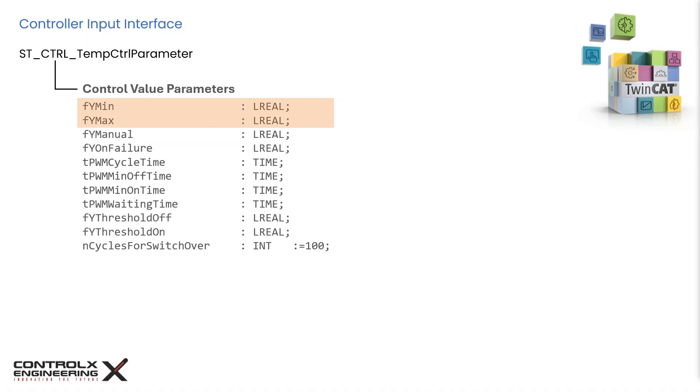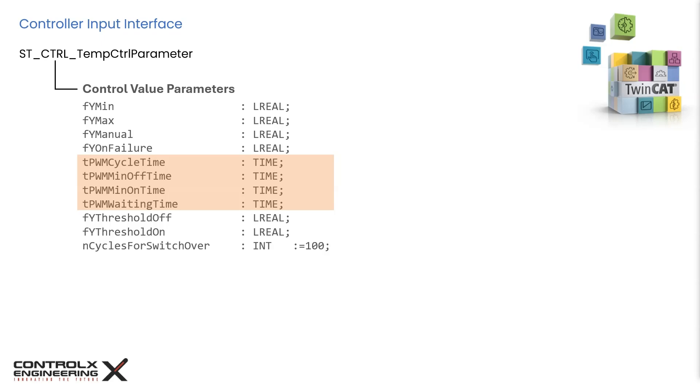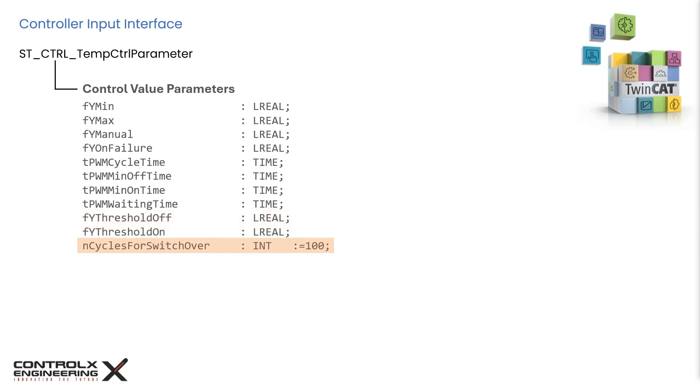These are the clamping limits of the analog output, also known as control value. You can use these settings to limit the control value within certain min and max values, depending on your application. You can use this input when the controller is switched to manual mode, and you can specify the output control value manually using this input. This is the optional control value during a controller fault. These settings are for the PWM output of the controller. In most cases, solid state relays are used to control the heater elements by using pulse width modulated signals to precisely control the temperature. Using these settings, you can specify the PWM cycle time, minimum switch off times and on times, waiting time when switching from heating to cooling. These are the inputs for a three-point control to specify the switch off and on threshold percentage. This is an integer value that specifies the number of cycles for transition from one primary set to another.